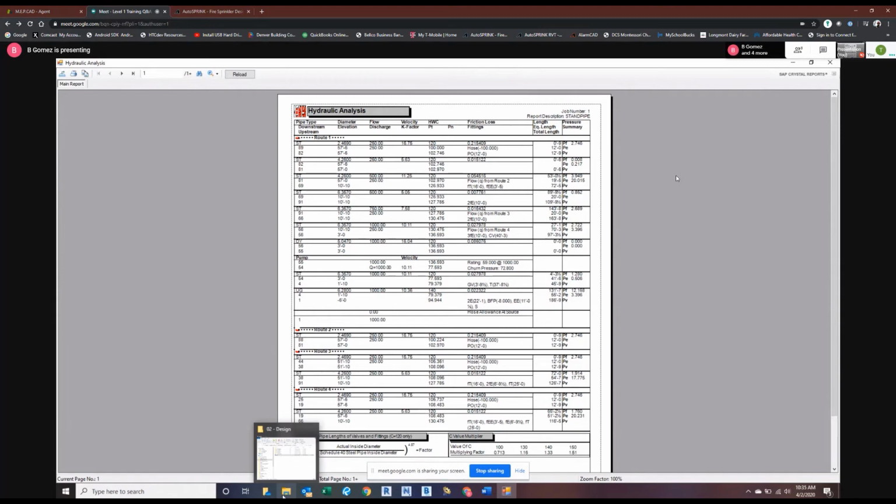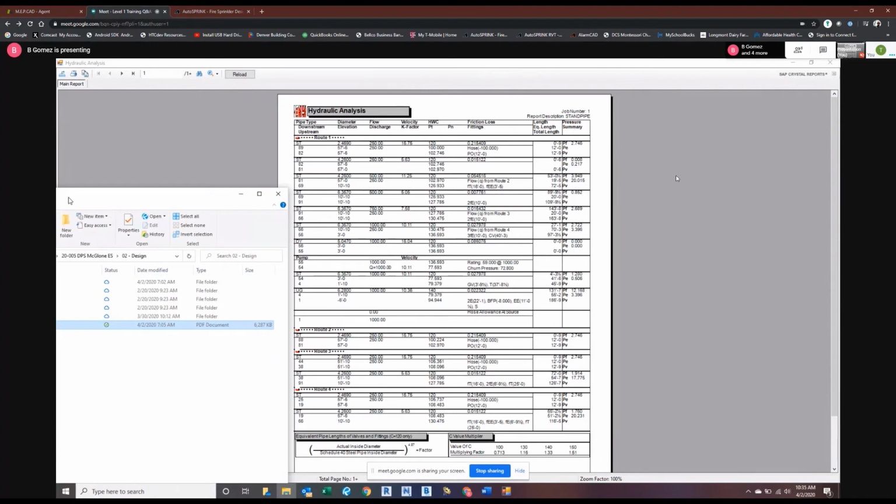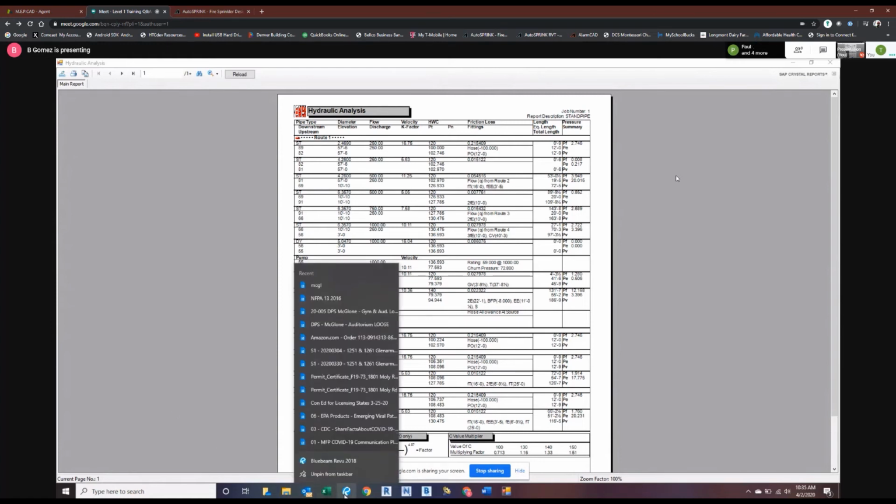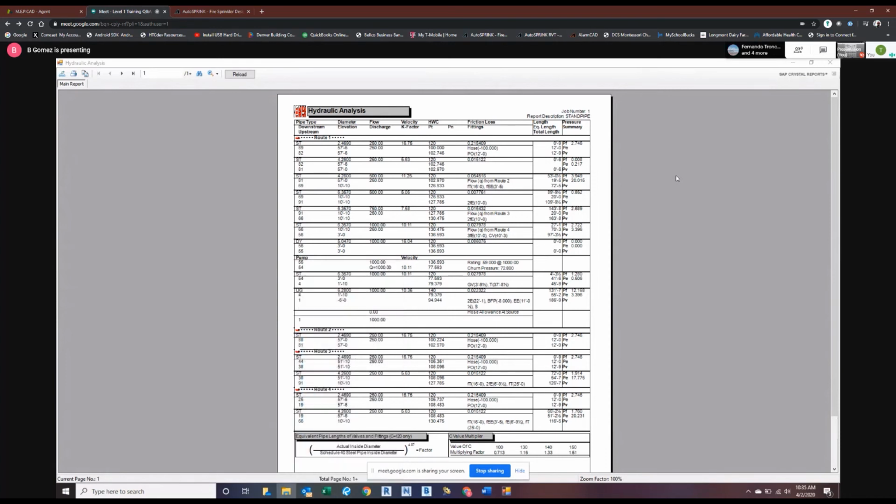You know what? I think you're absolutely right. Now that I think about it, looking back at the as-builts, I think the demand was a lot less for those hose valves. So if you shave 35 psi off of your starting pressure, that's basically the negative safety margin that you're getting now. But again, now we're talking about replacing something, and a lot of fire authorities, when you replace something, they're going to say, oh, well, now you need to meet current code or current standards. They'll allow things to be grandfathered in as long as you're not replacing major components.